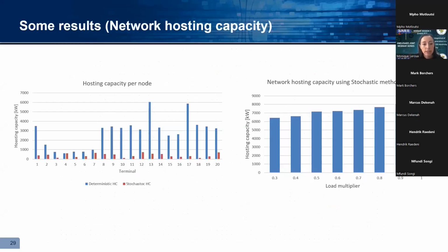And then this is just your hosting capacity per node, comparing the deterministic and the stochastic between each other. As you can see, your deterministic results show that you will have a lot more hosting capacity, or much greater hosting capacity using that method, because it only considers one bus in your system, one at a time. And your stochastic method will look at all your generation in your system. From that, you can see that your hosting capacity will be a lot less if you consider other generators in your network as well.